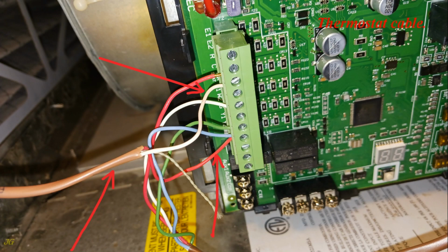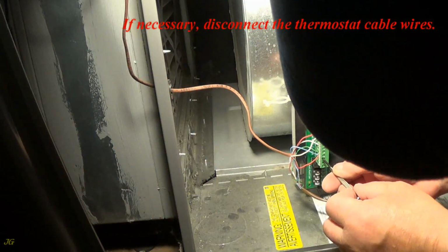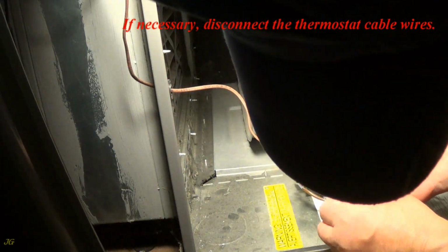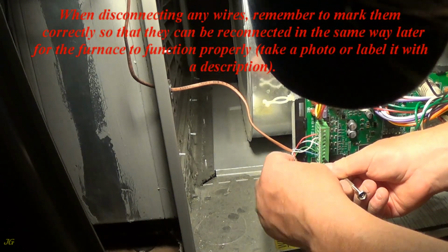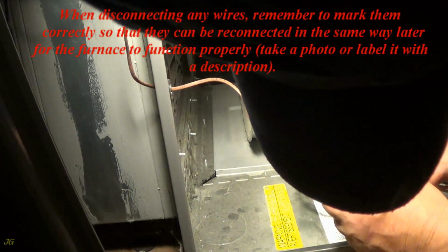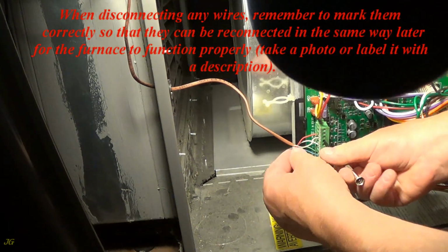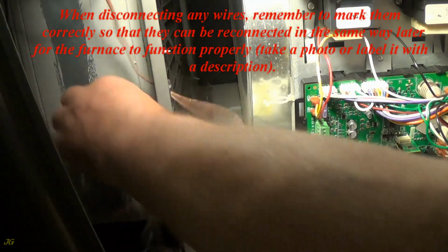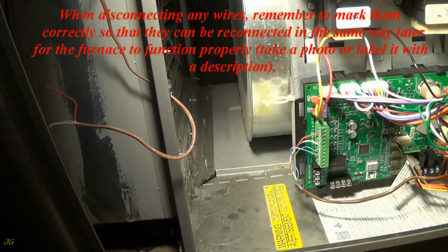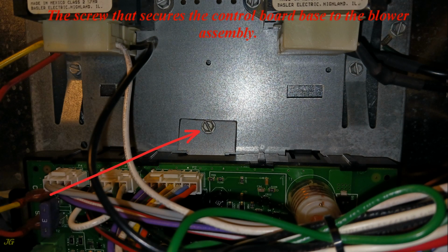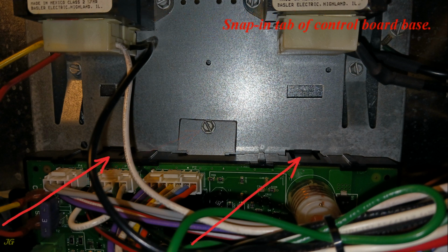Thermostat cable. If necessary, disconnect the thermostat cable wires. When disconnecting any wires, remember to mark them correctly so that they can be reconnected in the same way later for the furnace to function properly. Take a photo or label it with a description. The screw that secures the control board base to the blower assembly. Snap-in tab of control board base.